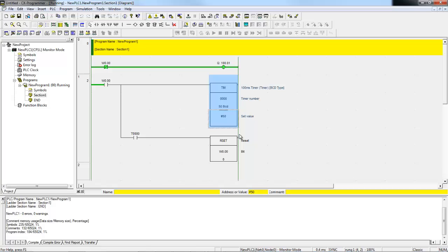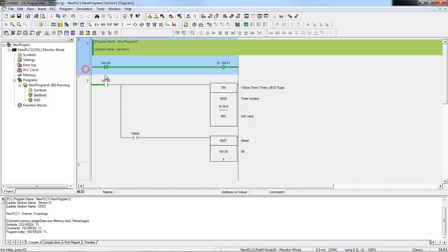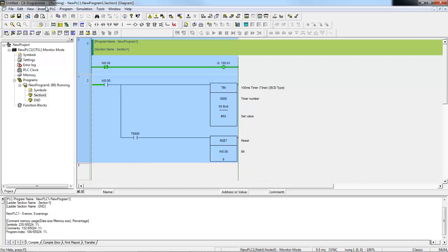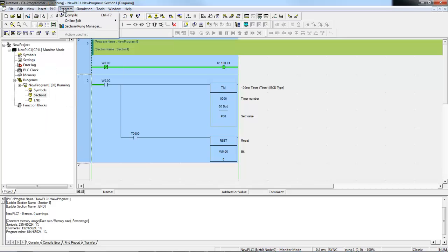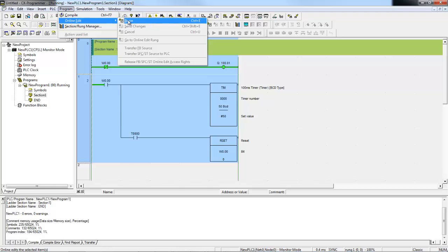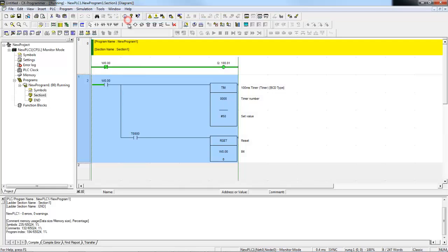The last thing I wanted to show you is an online edit. So sometimes we want to change just some simple logic in one of the rungs. So the way we would do that, I can select a rung or actually multiple rungs if you hold the shift button down. Then I go to the PLC menu, I'm sorry, the Program menu, Online Edit, and Begin.